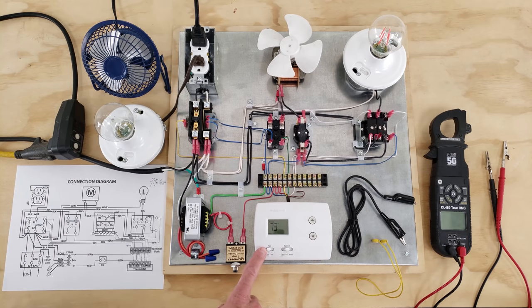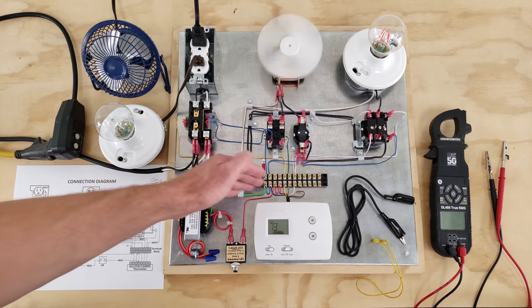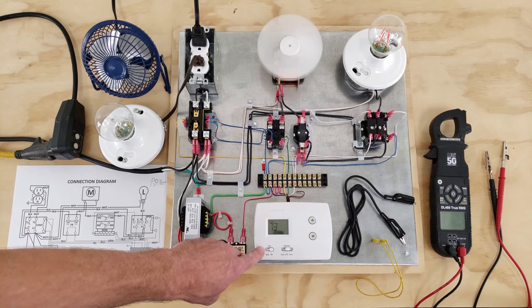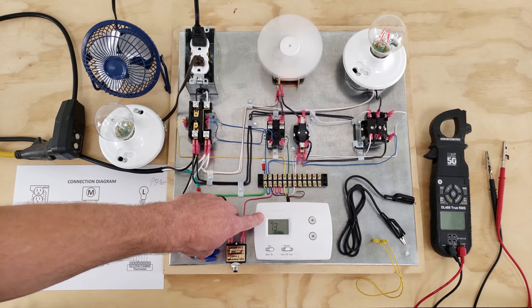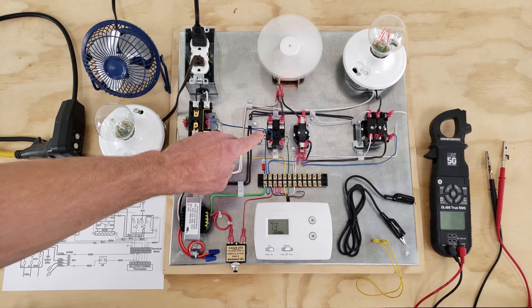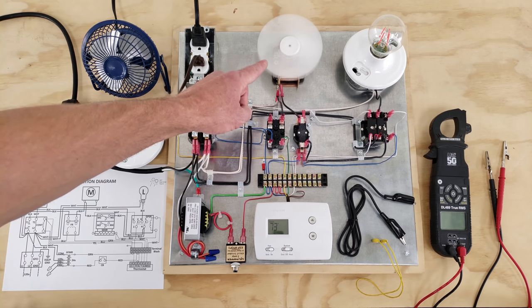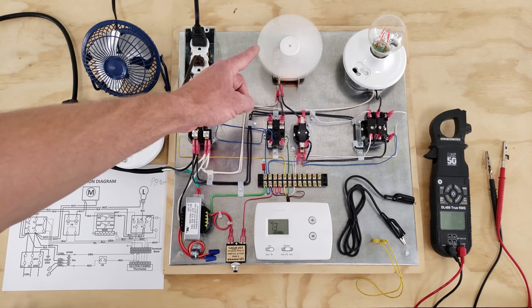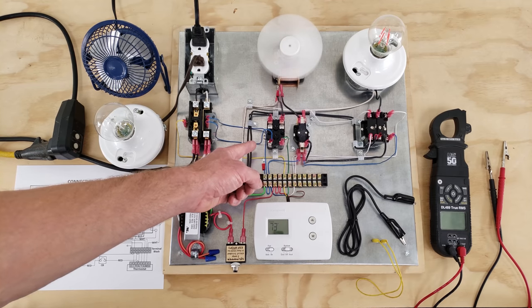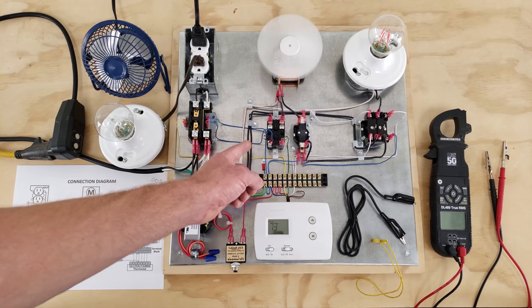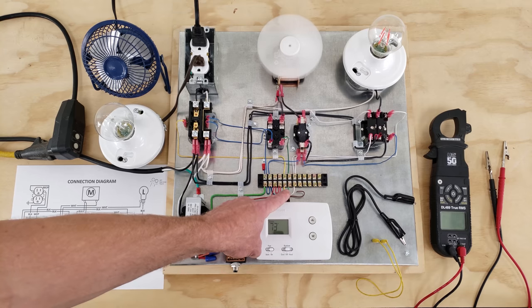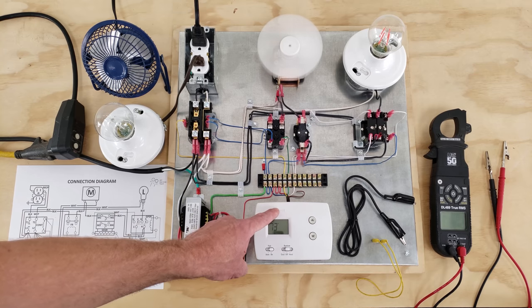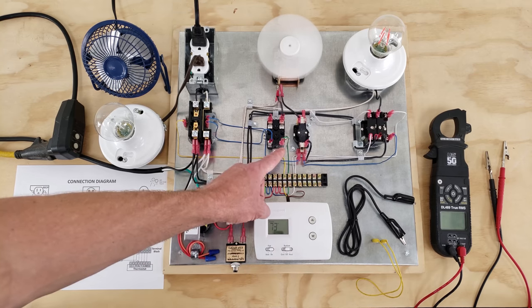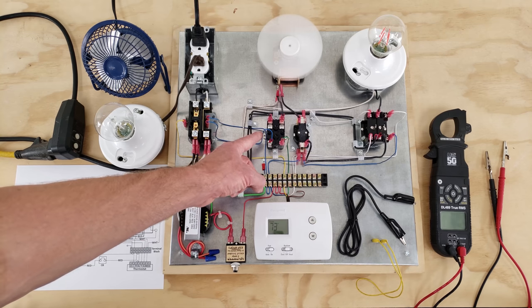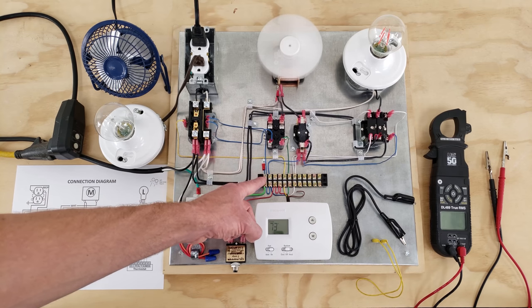So basically we have our thermostat wiring color code over here, and if you turn your fan to the on position, what's happening is we're using a fan relay to turn that fan motor on. That's a shaded pole 120 volt blower motor, and this right here is a 12 amp fan relay. And so what we're doing is we're utilizing this green wire coming out of the thermostat to power this fan relay, and this blue wire is the common coming back to our control board.